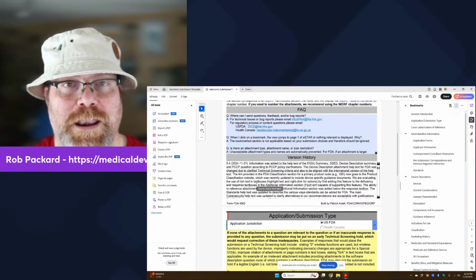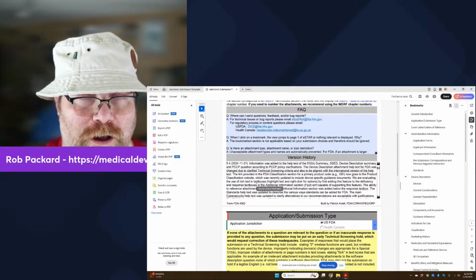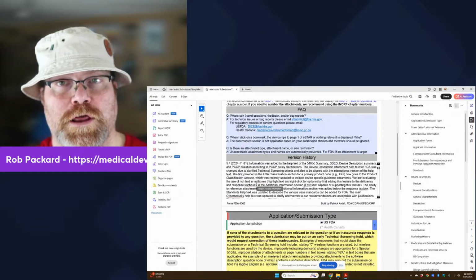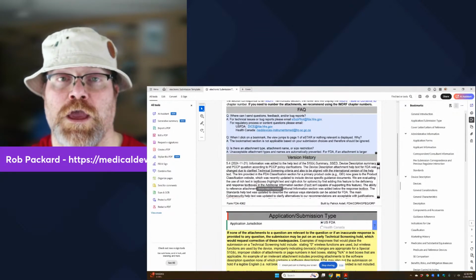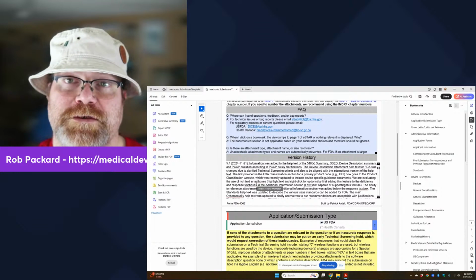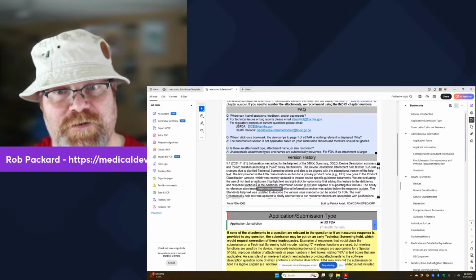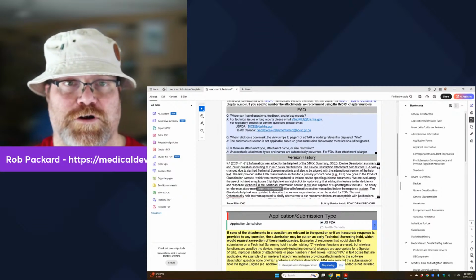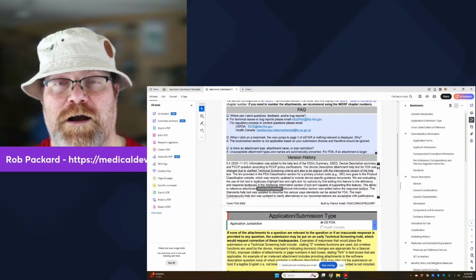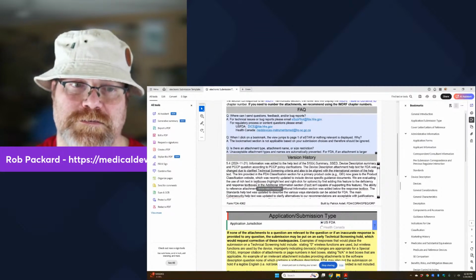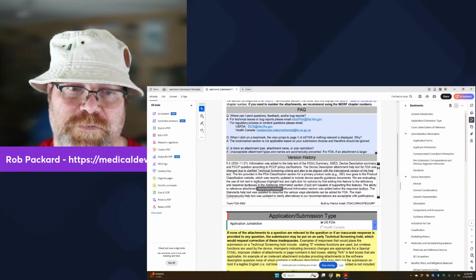But you are allowed to use 5.3. You're allowed to use 5.2. You're allowed to use 5.1. It's only when they go to 6.0 that you'll no longer be able to use the older versions of 5. You also cannot use version 4.3 because that's obsolete. They went to 5.0. So you can use any 5 series of the eSTAR template until they release the 6. And they release these fairly often because it's software and there are bugs, and there are always updates to other software that it interacts with, so they have to make adjustments.